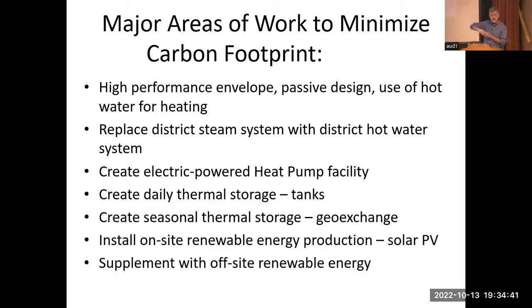We'll replace our district steam system—I'll show you a map of steam going all over campus to heat it—with a hot water system, and we're well on the way. We will create an electric powered heat pump facility, and daily thermal storage tanks, which we've actually built. We're just doing the hydro testing now.